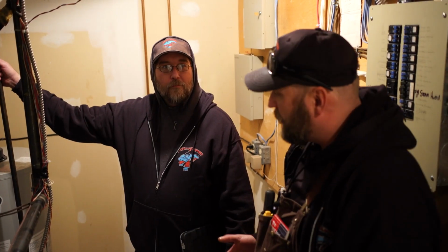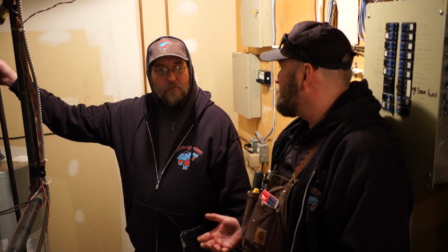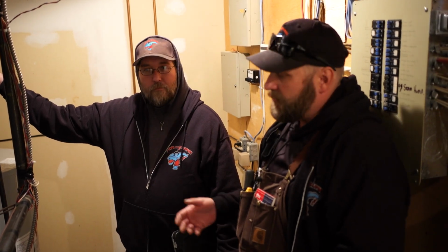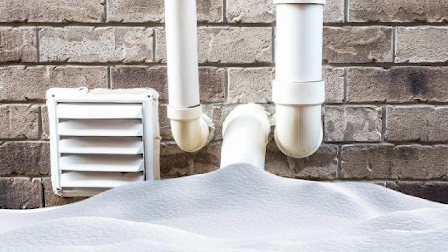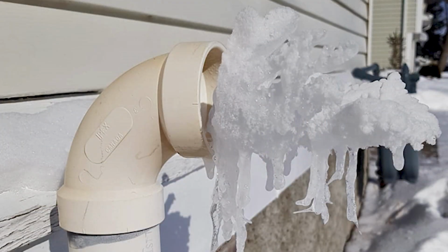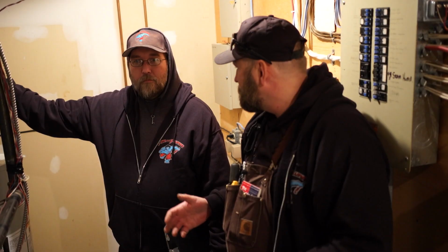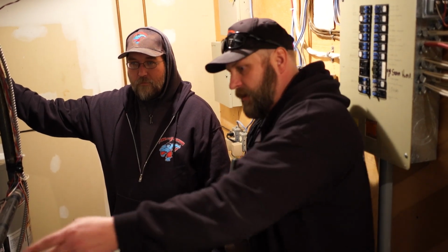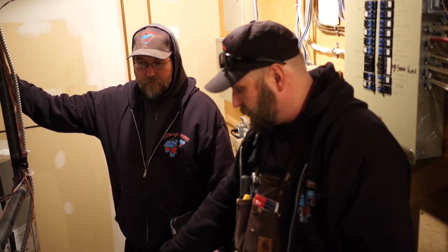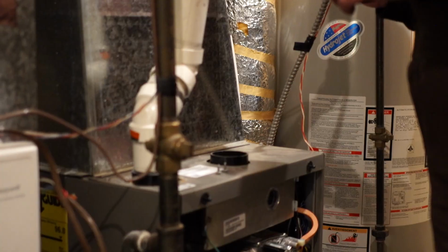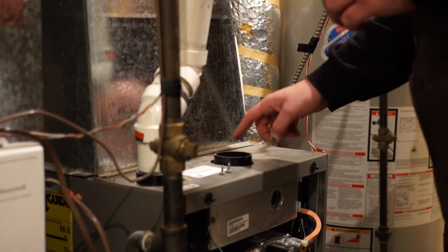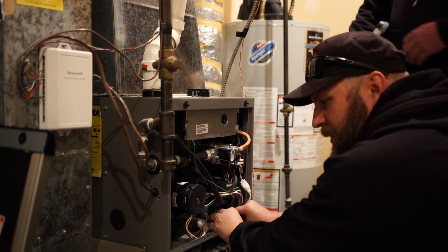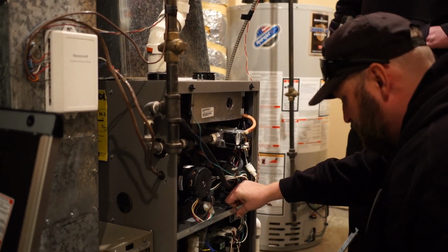One of the other things that can cause a pressure switch to fail is an obstruction in the venting or the intake, the combustion air exhaust piping on your house. As that goes to the outside of the house, you can find icicles, leaves, Hot Wheels cars, hockey balls, and all sorts of stuff that can get plugged in there. If that isn't moving properly, the pressure switches will fail and your furnace will not fire. Just a leaf the size of a dime can block that — kills it.